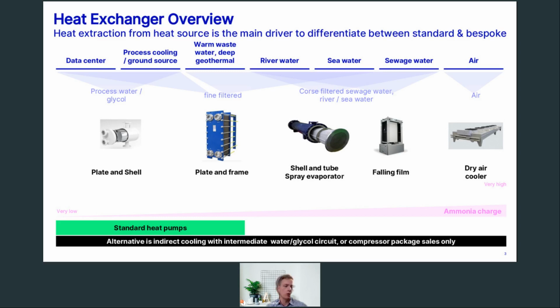But the bit about ground source is that it's not always completely clean. There are some particles in it, and you want to make sure that the particles don't get stuck in your heat exchangers. There are different ways to solve this: filtration, backflush and so on, which I will get back to. But another solution, if there is increased fouling of the water, is shell and tube or falling film, where you don't have the build-up of material in the heat exchanger. You are able to clean the heat exchangers while in process. So we do all these specialized solutions also to optimize the efficiency of the heat pump solution.